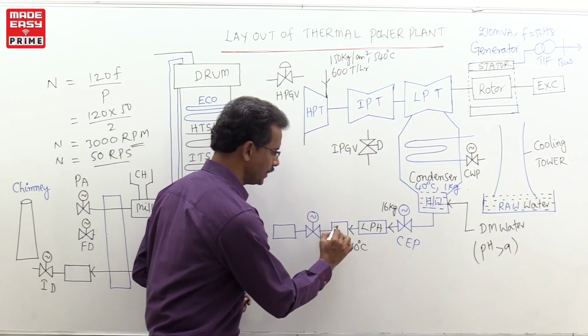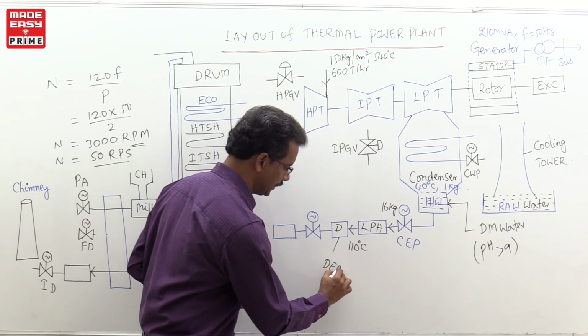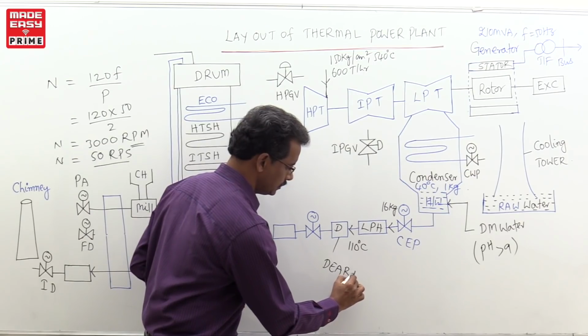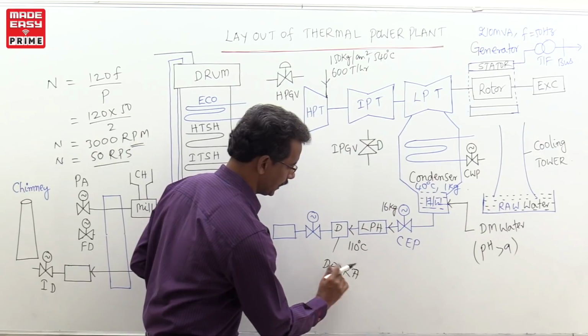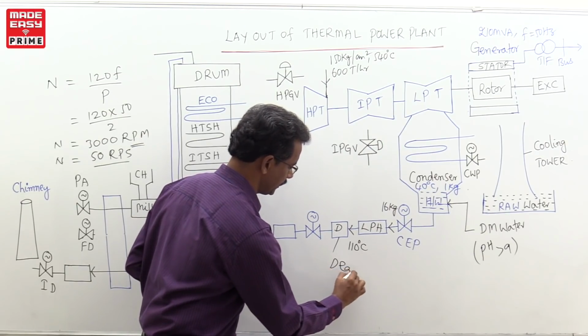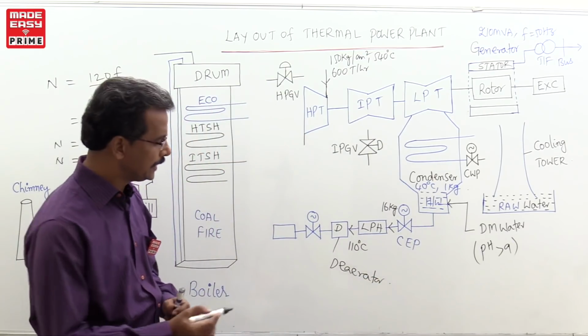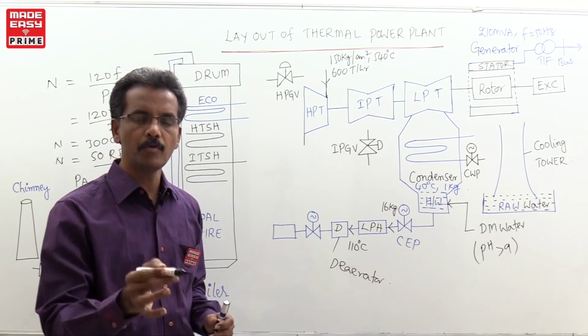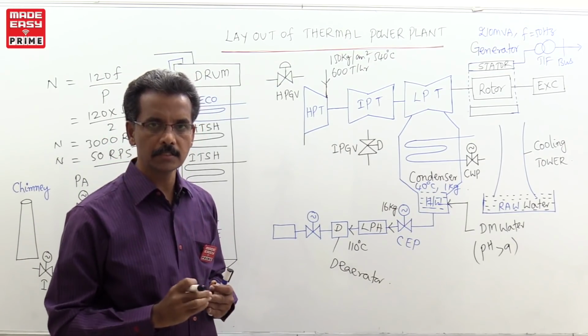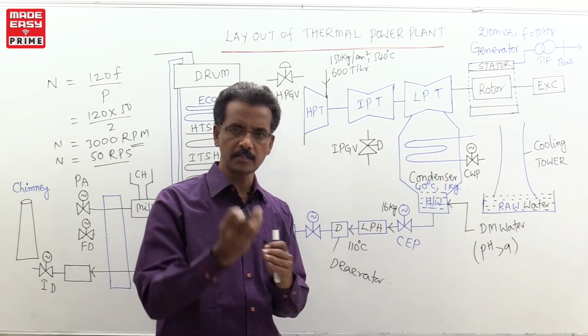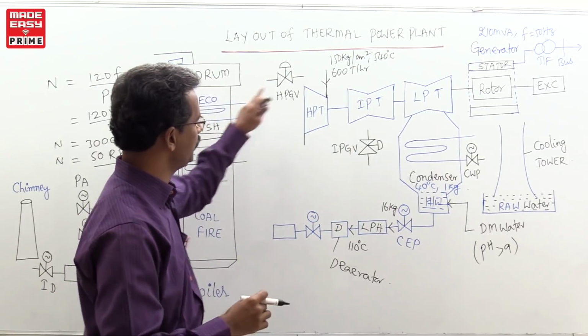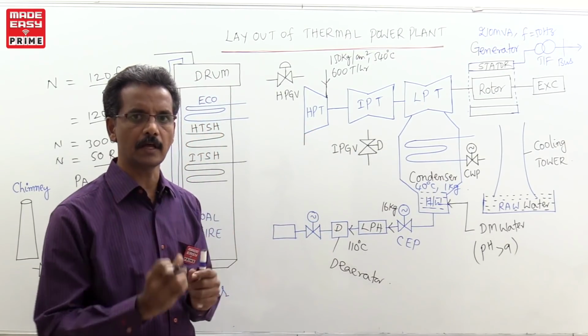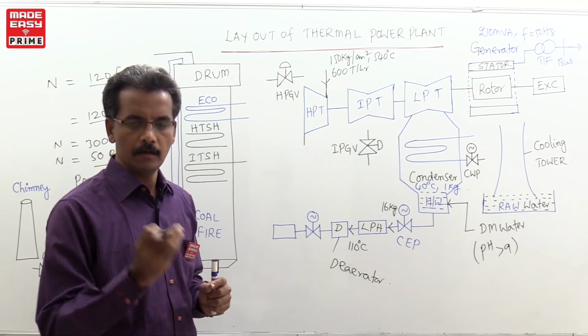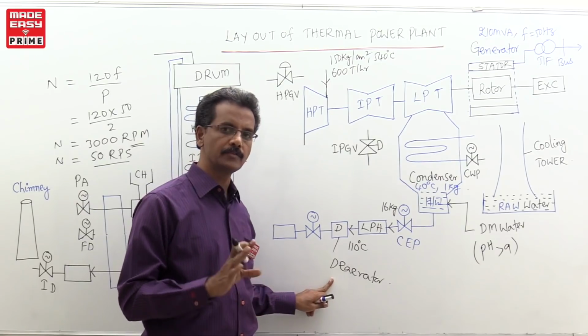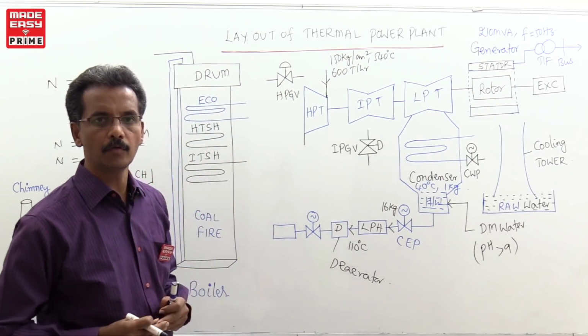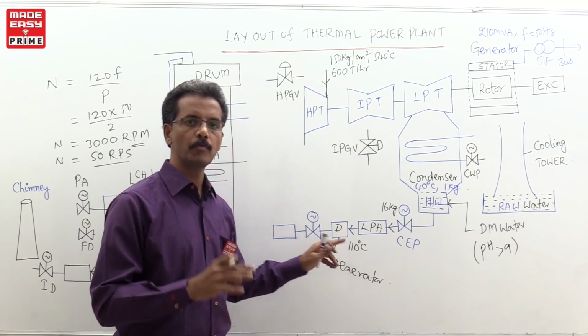And it is passing through one of the areas called the deaerator. I am writing this name because, from the interview point of view, this is actually asked. This deaerator, the meaning of de-air, is removing the dissolved gases or air bubbles inside the water. If these air bubbles or dissolved gases available inside the water are sent into the turbine, the turbine blades will get damaged. For protection of the turbine blades from these air molecules, we are supposed to use this deaerator. This is one important device from your interview point of view. It is used for removing air molecules.